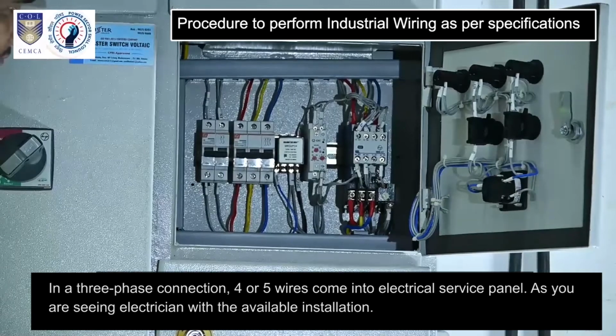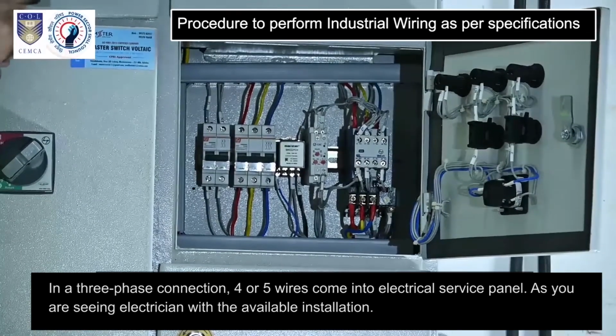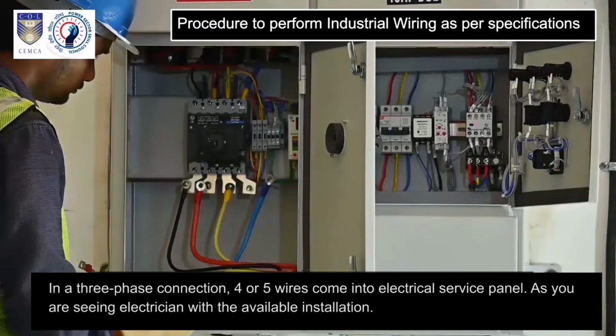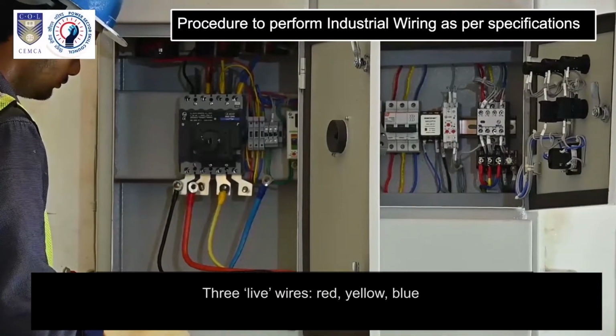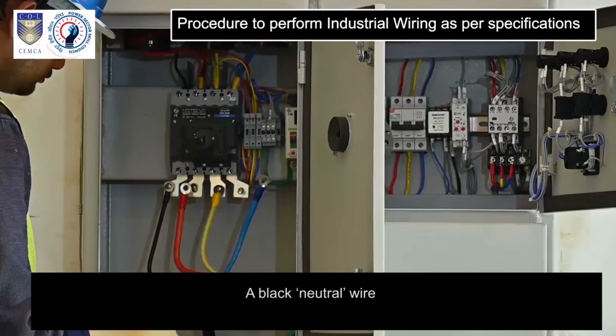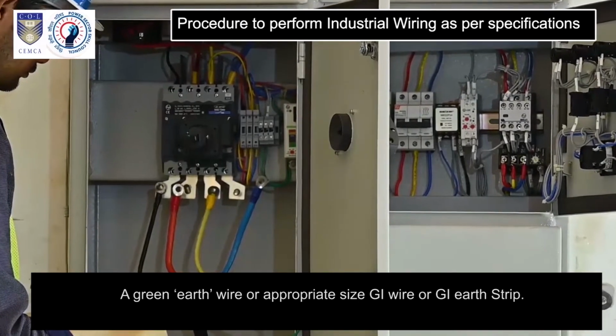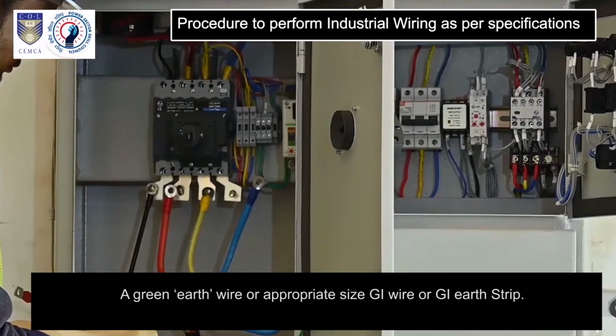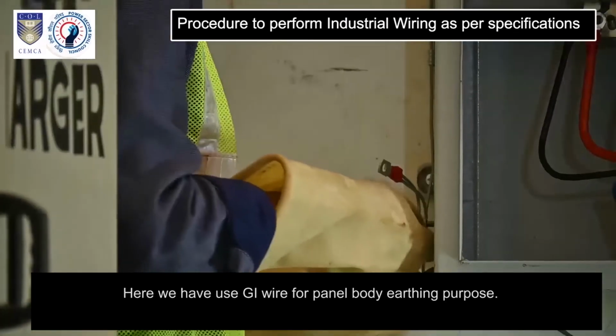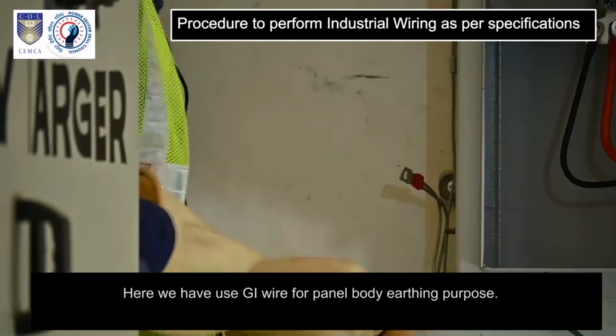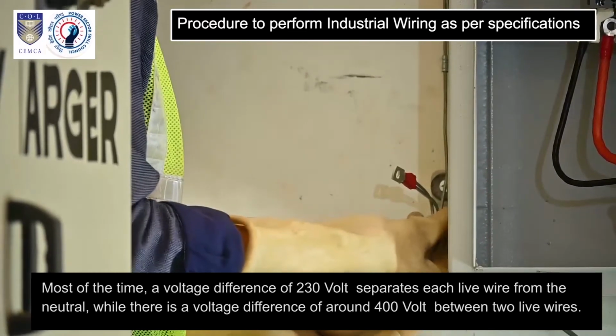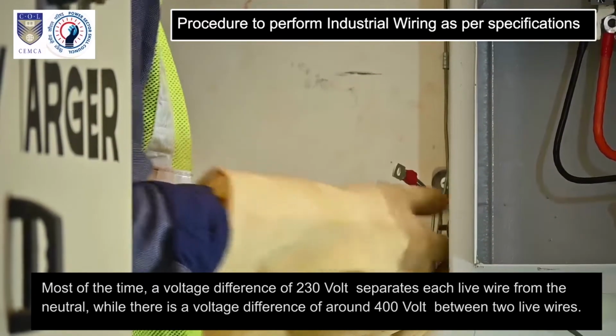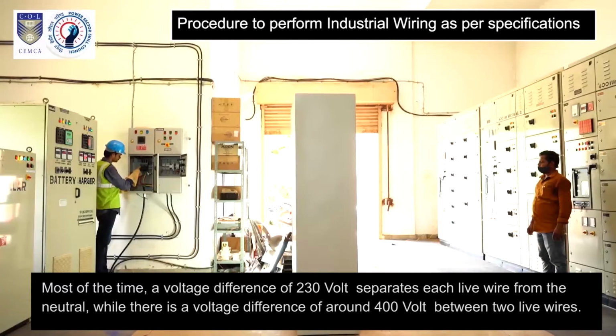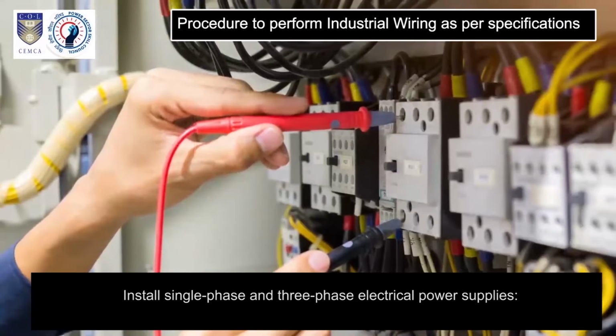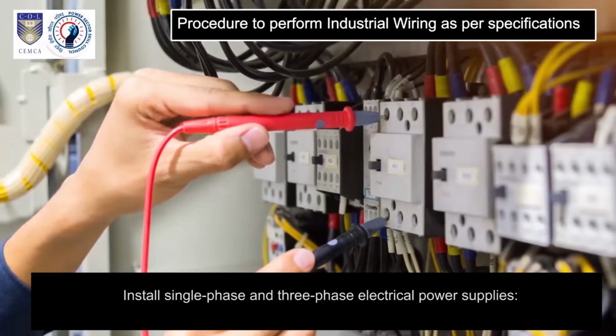In a three-phase connection, 4 or 5 wires come into electrical service panel. As you are seeing, the electrician with the available installation: 3 live wires, red, yellow, blue, a black neutral wire, a green earth wire or appropriate size GI wire or GI earth strip. Here we have used GI wire for panel body earthing purpose. Most of the time, a voltage difference of 230 volts separates each live wire from the neutral, while there is a voltage difference of around 400 volt between two live wires. Install single-phase and three-phase electrical power supplies.